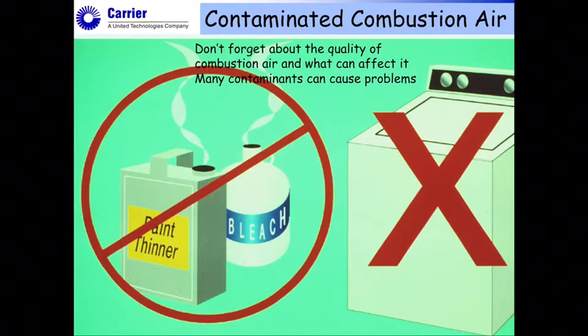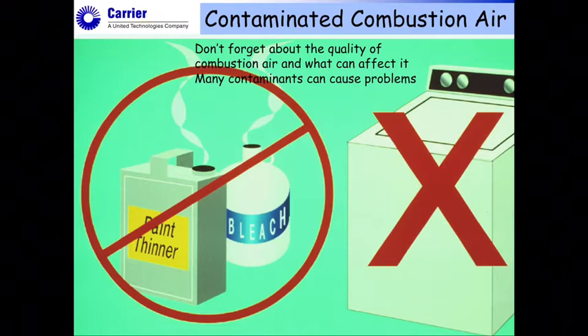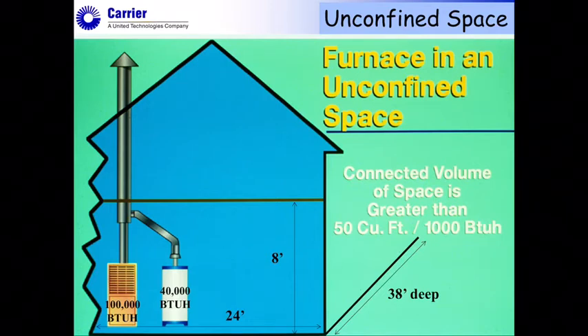We also need to consider contaminated air, because the quality of combustion air matters. You could have air contaminants such as chlorinated bleaches, paint thinners, salt blocks, dryer sheets, or even a refrigerant leak. These contaminants can cause combustion issues and actually deteriorate the vent system because of the acids created when these substances are burned.